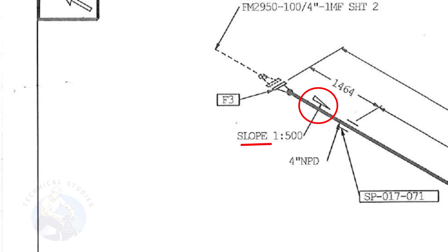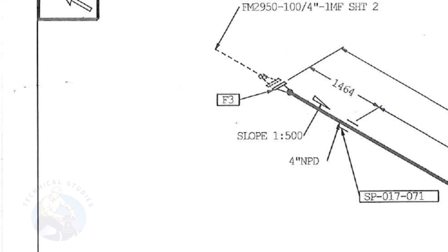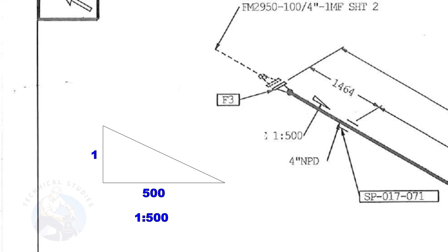This symbol shows the slope and the slope ratio. It means the slope is towards the south direction. The slope ratio 1 to 500 means for every 500 millimeters length of the pipe, one end of the pipe will be 1 millimeter lower than the other end. Suppose the length of the pipe is 2,000 millimeters, the slope will be 4 millimeters.